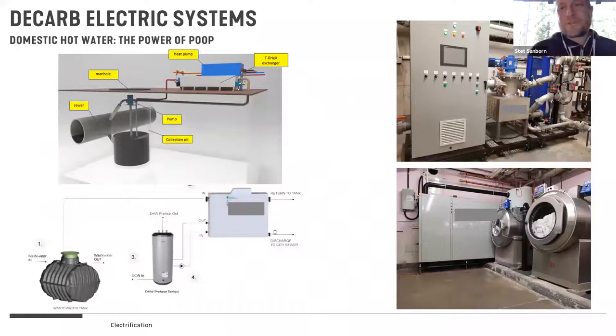The whole discussion around source energy though becomes really important in cold climates. We typically are looking at air source heat pumps or ground source heat pumps. And all of you guys in the Midwest that have cooling and heating load know the value of ground source heat pumps or geo exchange systems, and the value that has by dealing with a moderate temperature sink source, your COPs are amazing. You might deal with it on the pumping energy side, trying to pump all the fluid through your bores.